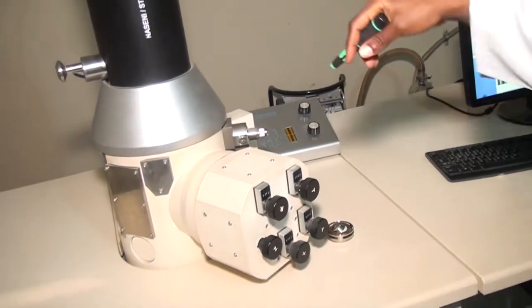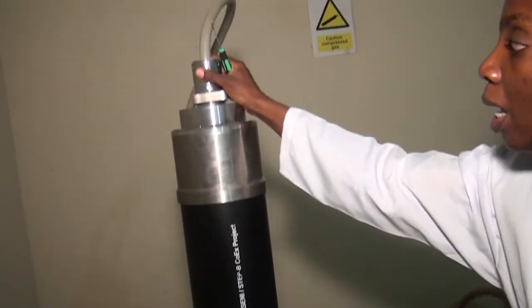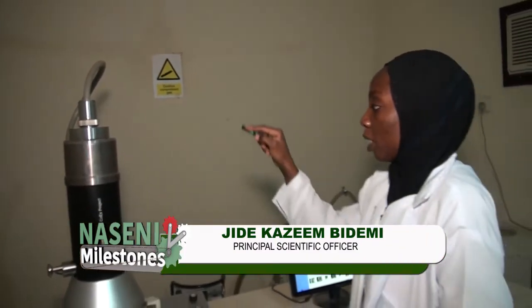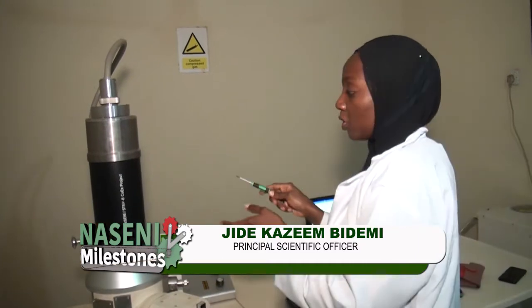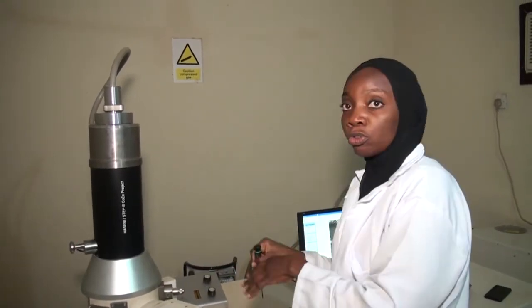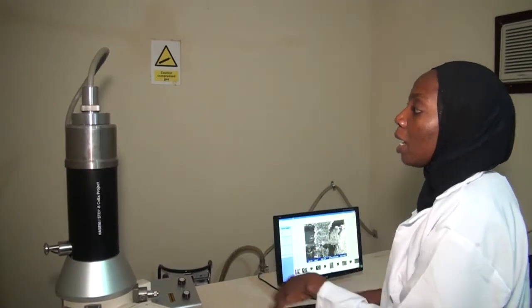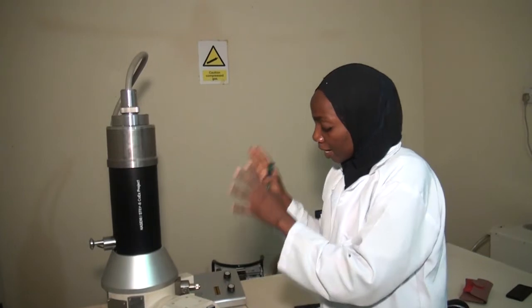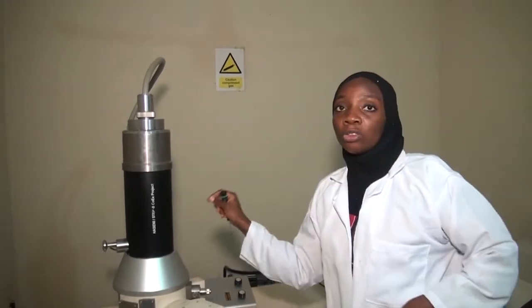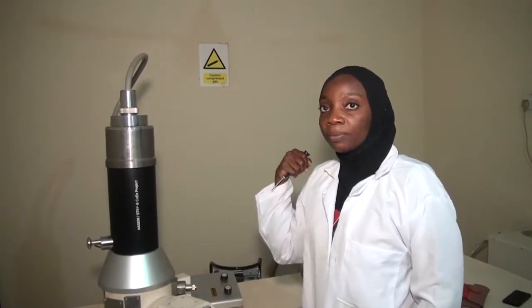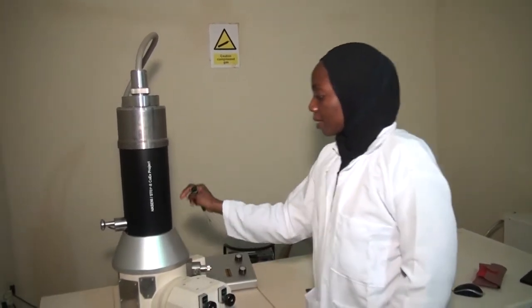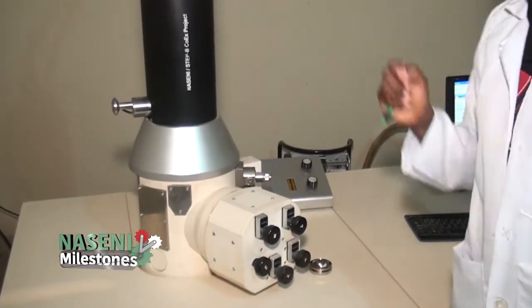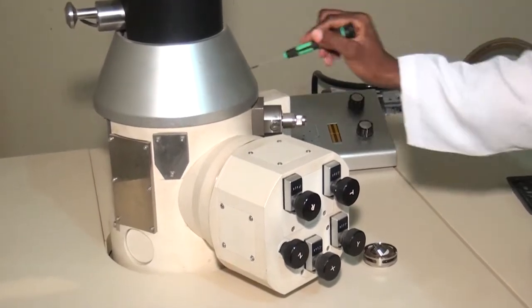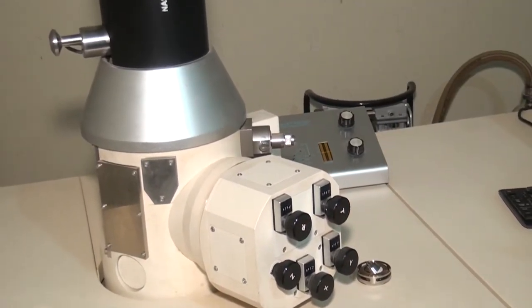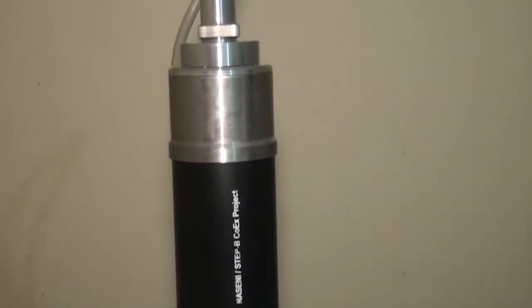In the system, electrons are generated at the top of the microscope, and they follow a vertical path in the microscope, held within a vacuum system. After that, the electrons travel through electromagnetic fields and lenses, and it is these fields and lenses that focus the electrons down towards the sample. Once the electrons hit the sample, electrons from the sample are ejected. There is a detector within the system. These detectors collect secondary electrons and backscattered electrons generated from the sample, and these are converted into a signal. The signal will be sent to this, and it will be captured in the form of an image.